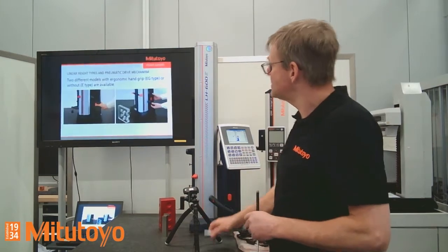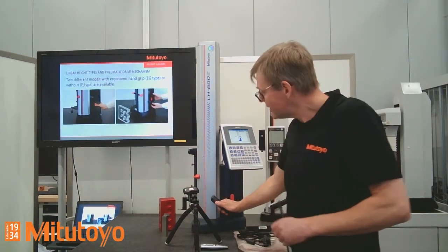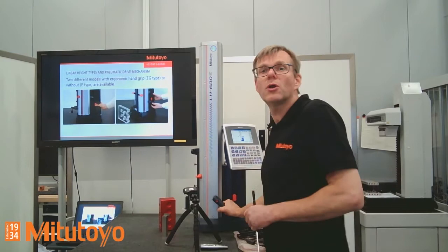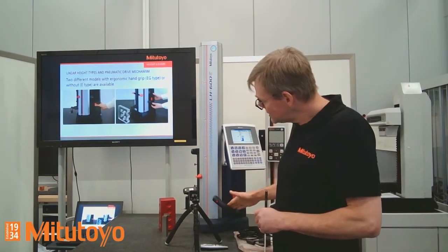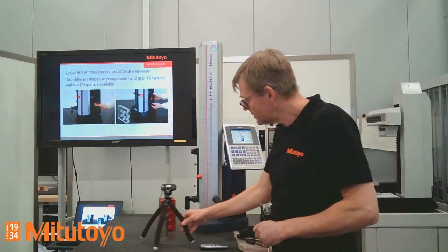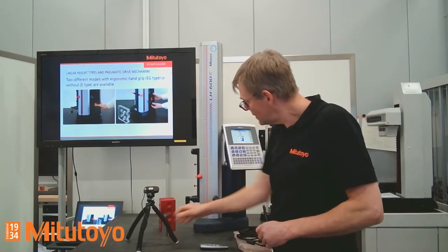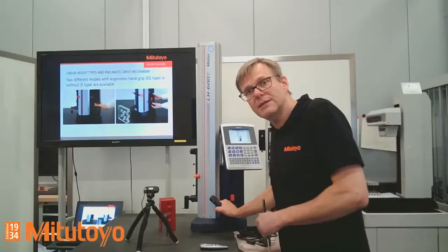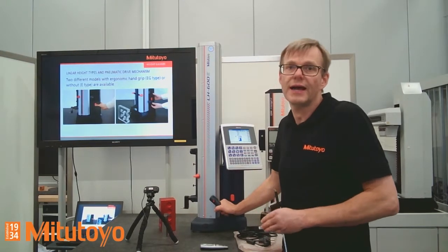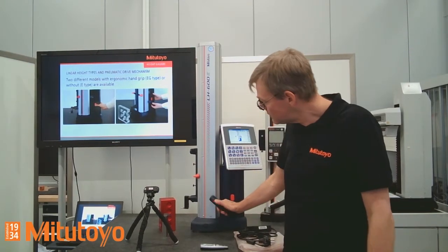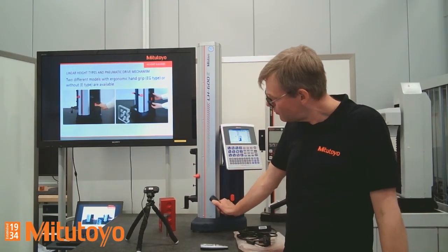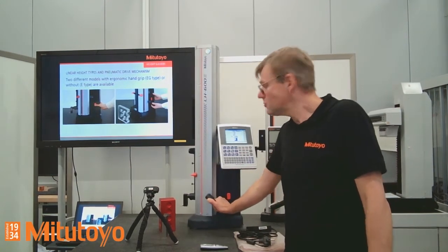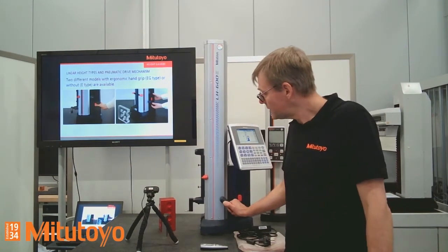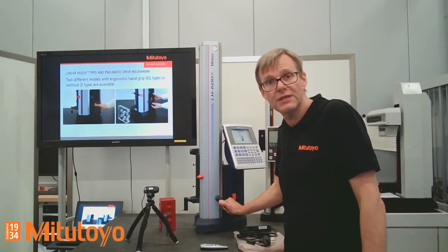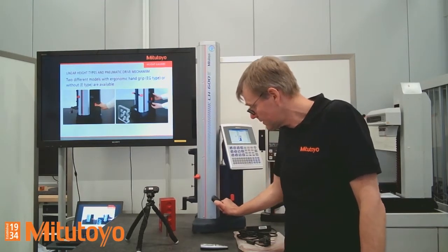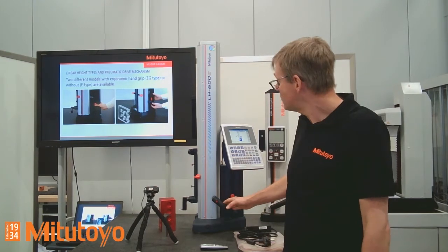So what is the next step? The Linear Height here on the table is the model with a grip. Here is a grip, and with this grip you can move the Linear Height on the granite table. Here is a switch, the red one. If you put on the switch, you can move the Linear Height with the air floating system very easily on the granite plate. That's the model we have here on the table.